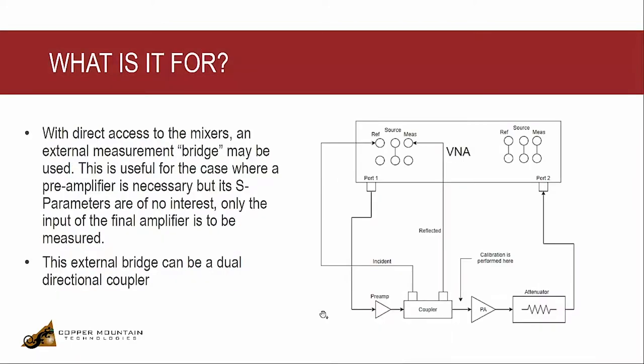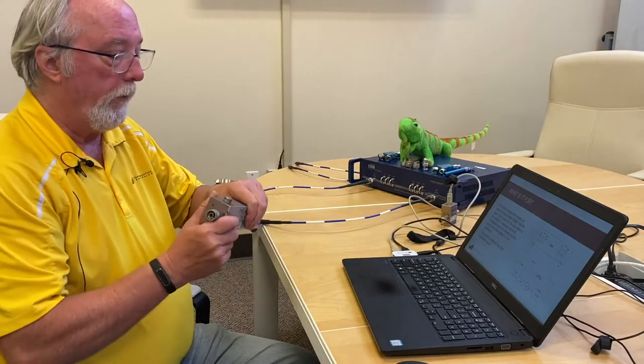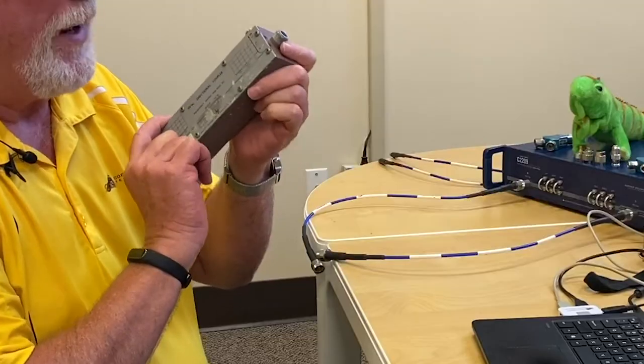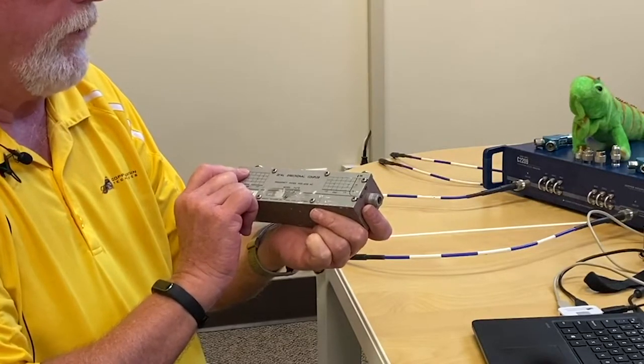So what's it for? Now that we've shown it, let's actually hook one up. With direct access to the mixers, we can put a bridge, and we're going to use this coupler. This is a bi-directional coupler, 1,900 to 4,000 megahertz. It's a 20 dB coupler.